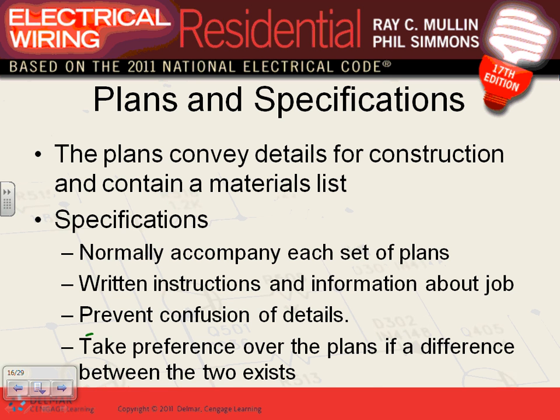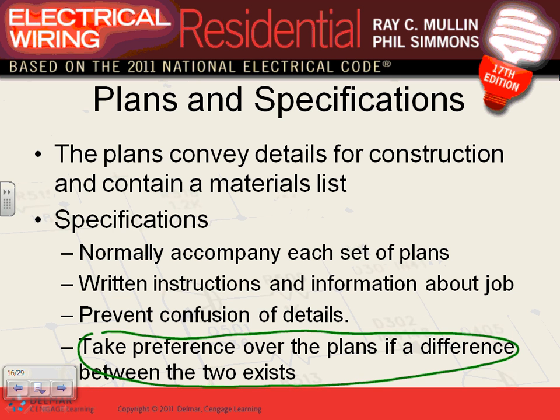This is what I want to highlight. If there's a difference between the plans and the specification, the specification always rules. For example, if my specification says the minimum conductor size is number 12, and the plans show a number 14, and the installer wants to put number 14, I say no, my specification says number 12, then the specification takes over the plans. You'd hope they wouldn't do that, you'd review your plans and put everything as number 12, but if there's any conflict, specification rules.